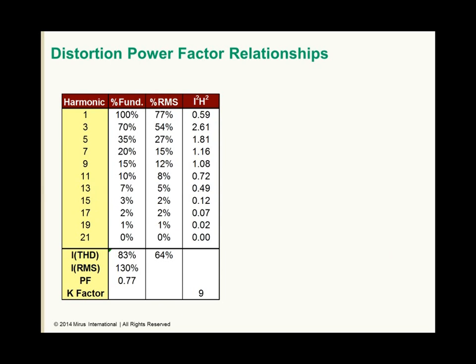To show this relationship, I've created this table which provides some values for a typical nonlinear load. So in this table we've got our harmonic component. We show the odd harmonics, because those are the ones that are most predominant in our power systems. Then we have a column with the harmonics as a percent of the fundamental component. This is typically the way harmonics are measured or indicated in North America, South America. There's also a percent RMS value that we show, and that's typically used in Europe and other areas of the world. In this column with percent fundamental, the 60 hertz or 50 hertz fundamental component is going to be 100%.